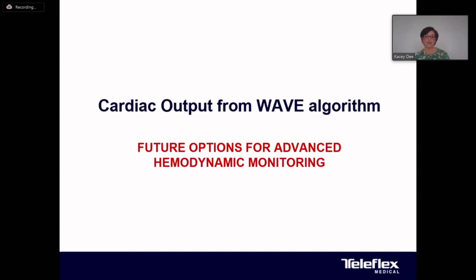Current practice has recognized the need for hemodynamically guided treatment in heart failure using monitoring tools such as thermodilution and related parameters. As a result, we have determined that the wave calculation of flow on the Arrow systems, which is currently used for intrabeat timing, can be calibrated to provide a measure of the beat-to-beat stroke volume and therefore cardiac output. This type of algorithm would provide clinicians with immediate hemodynamic monitoring from the start of balloon pump therapy to determine if the patient is a responder or requires escalation of therapy.